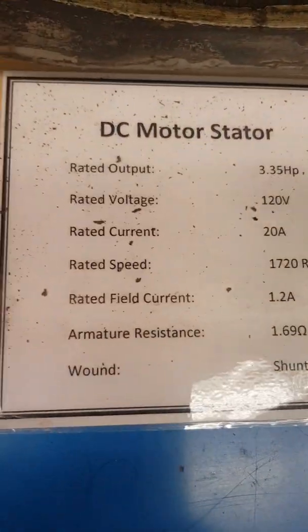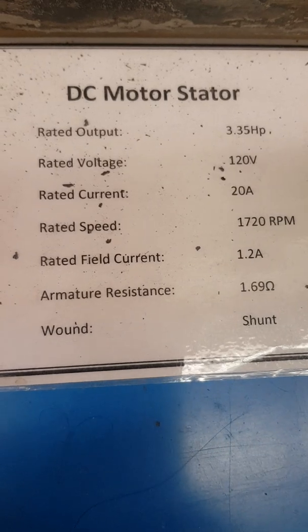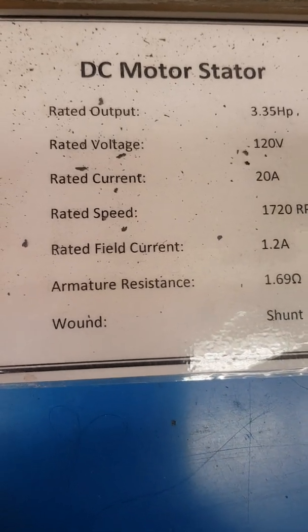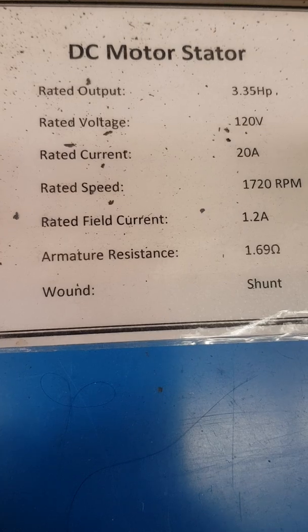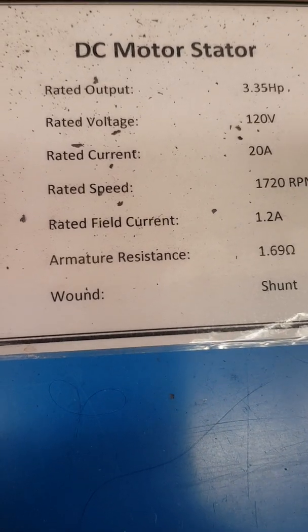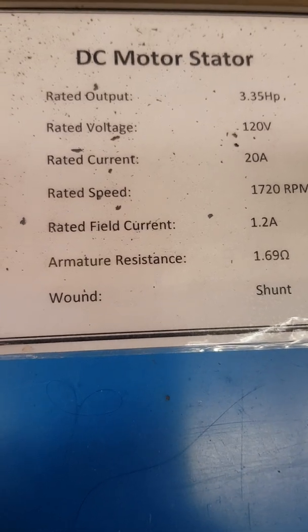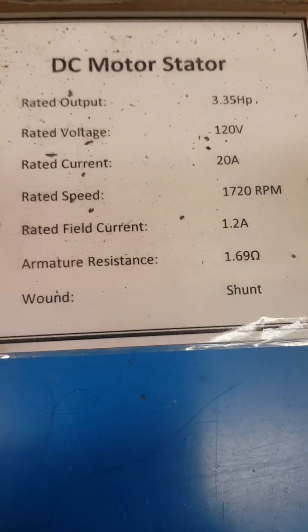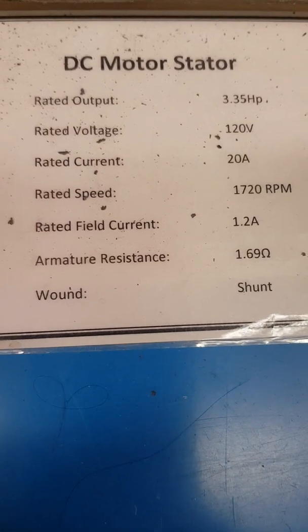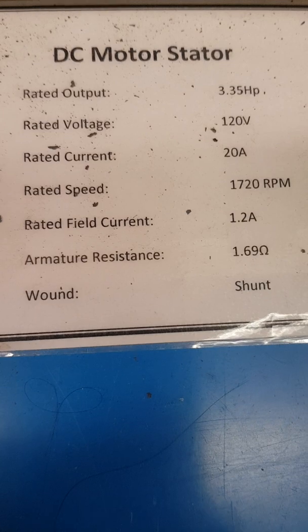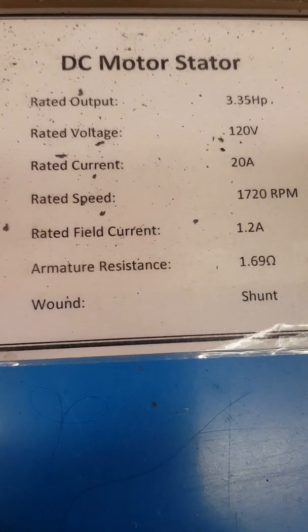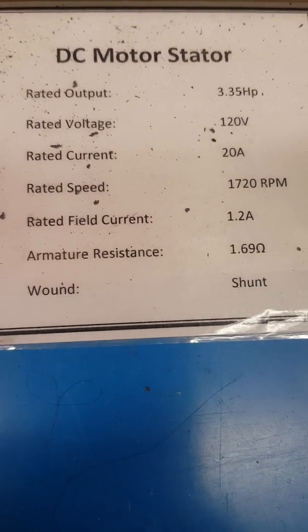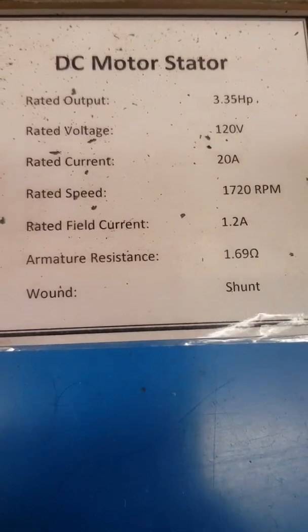This is the most important information we need to know about the motor. The rated output is 3.35 horsepower, which is basically around 2.5 kilowatt. The input voltage is 120 volt DC, the rated current is 20 amps — this is the summation of both the field current and the armature current. The rated speed is 1,720 RPM, and the field current is 1.2 amps. So the armature current is 20 minus 1.2, which is 18.8 amps. The armature resistance is 1.69 ohm.